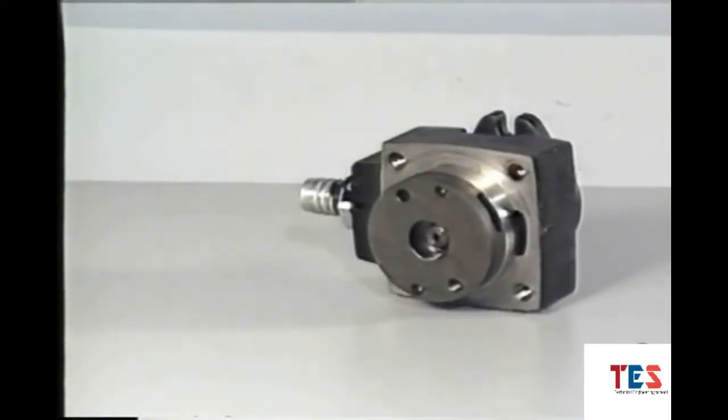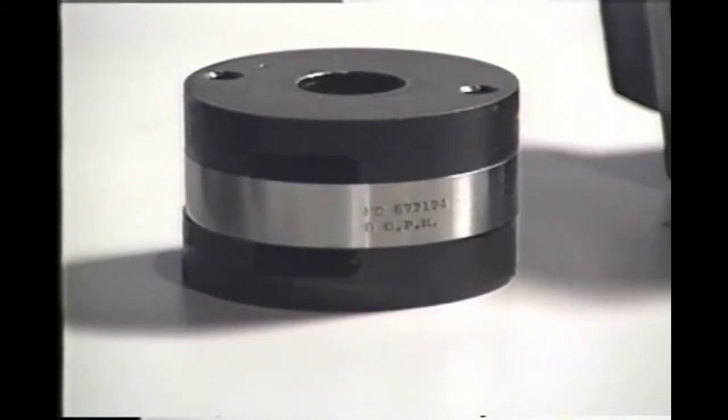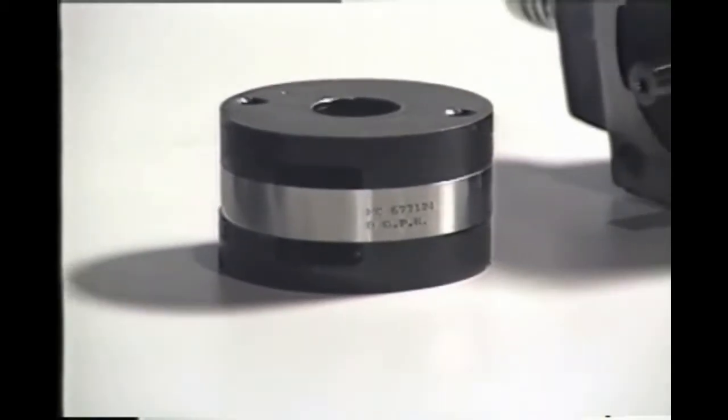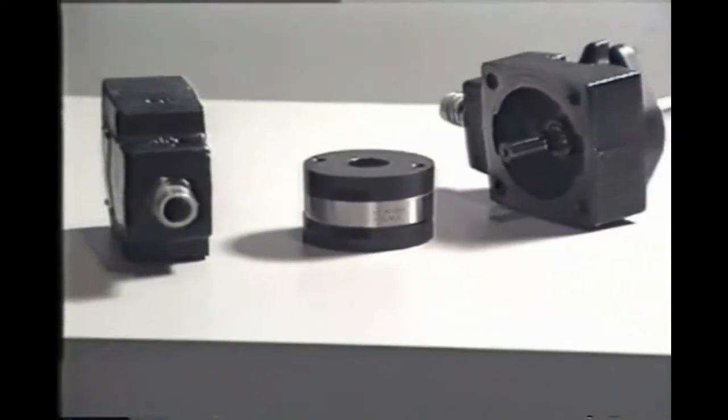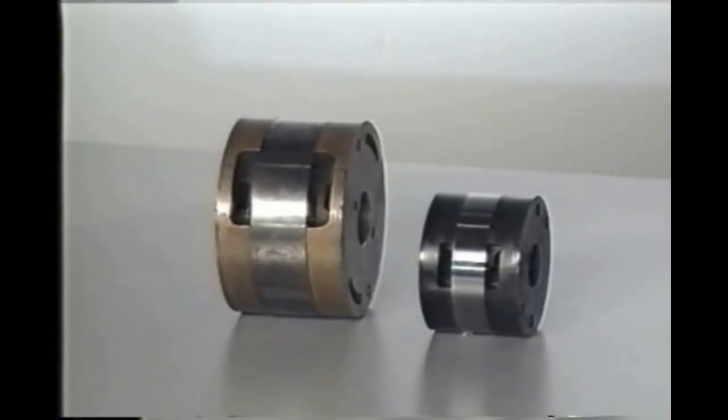When this portion of the pump wears out, it can be repaired by simply replacing the whole cartridge assembly. Within certain limits, the pump volume can be increased or decreased by replacing the cartridge assembly with another one of larger or smaller volume but with the same outside dimensions.